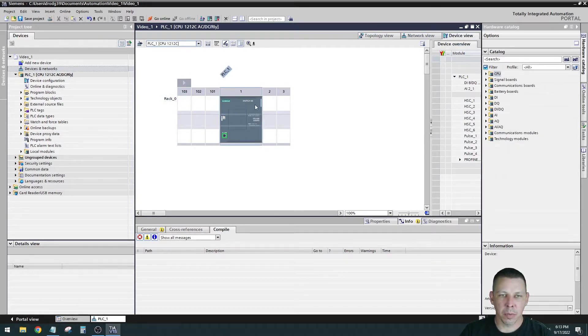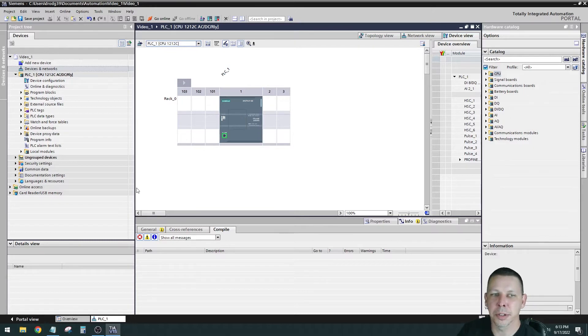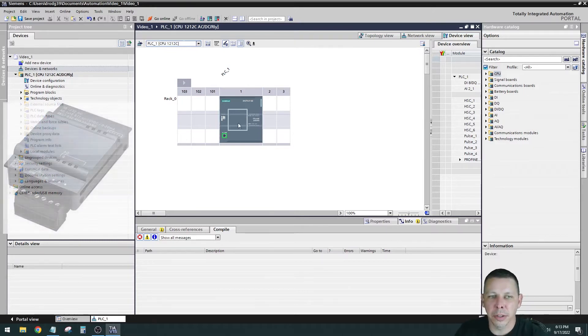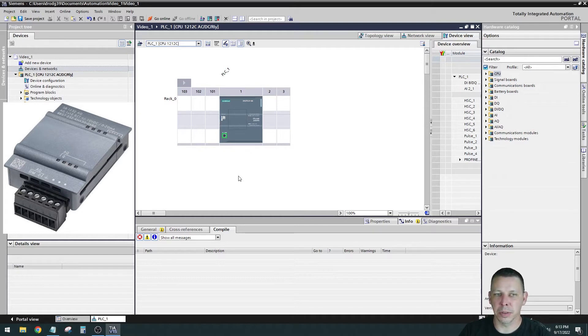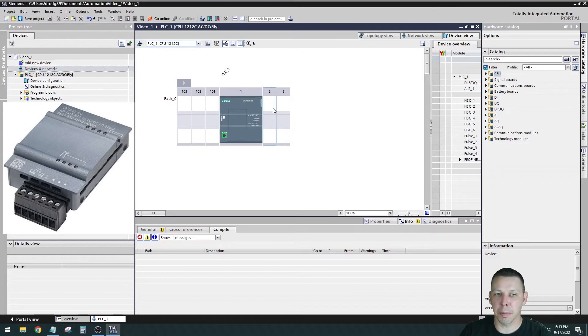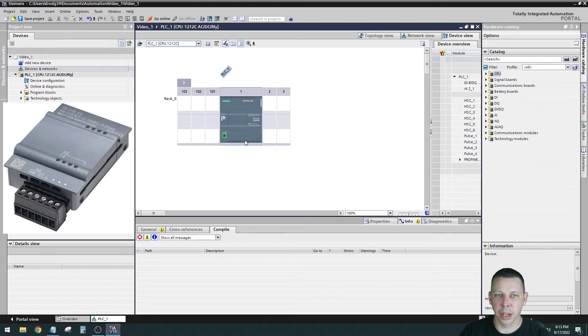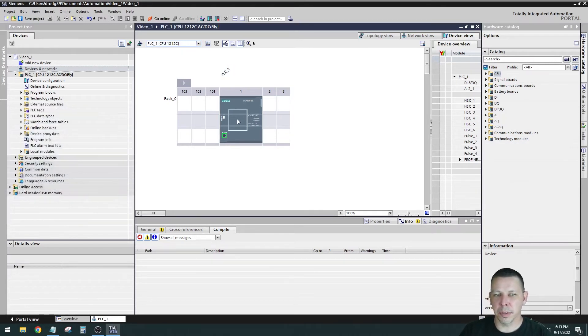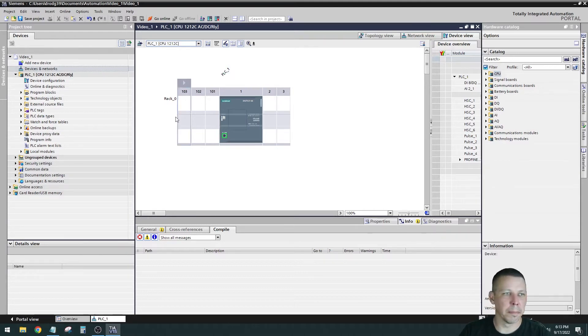When you're trying to select it from this view, this is a separate module. I'll drop a picture of what that looks like. This little square that's blank can pop off. It's a physical piece on the processor, a piece of plastic, and you can pop it off and put an add-in module in there. You can add modules on the side - communication modules usually go on the left and IO modules go on the right. This one in the middle, the only ones I've used have been analog inputs and outputs, but I know they make other versions.